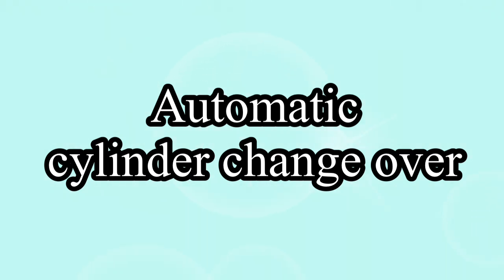A new 1,000 parts per million nitric cylinder, when it is switched on, reads 150 bar on the pressure gauge. When this drops to 30 bar, the cylinder icon on the front display changes from blue to yellow and then will turn red when the cylinder empties.